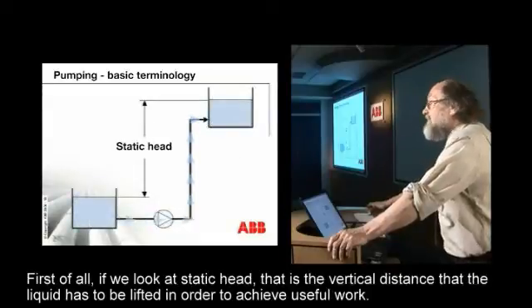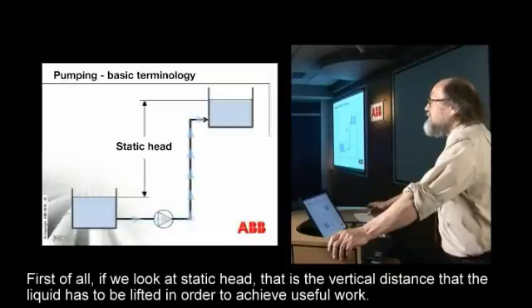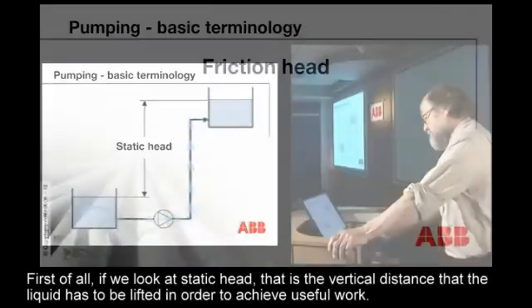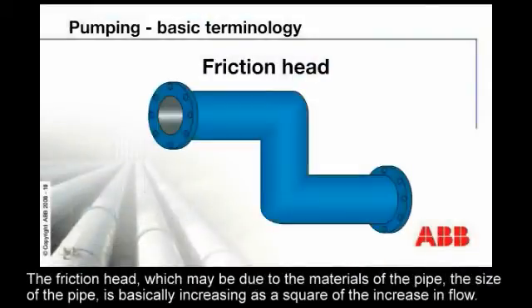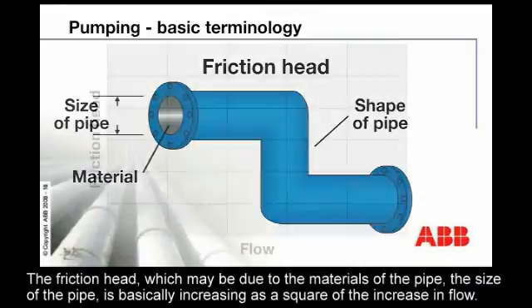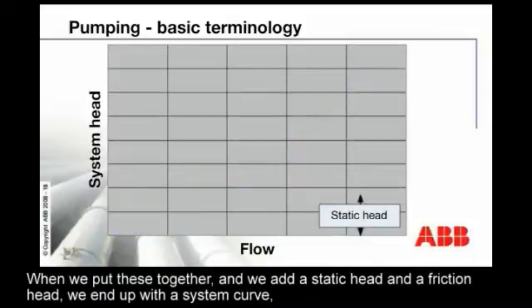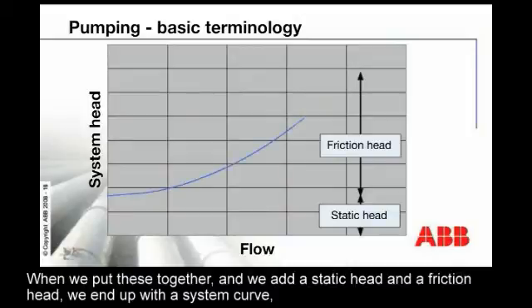If we look at static head, that is the vertical distance that the liquid has to be lifted in order to achieve useful work. The friction head, which may be due to the materials of the pipe or the size of the pipe, is basically increasing as a square of the increase in flow. When we put these together and add the static head and the friction head, we end up with a system curve.